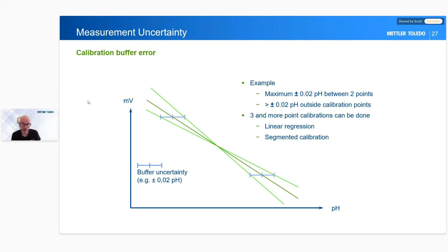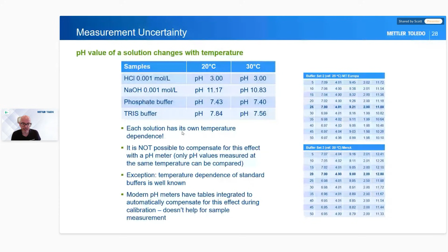The same with temperature. Each sample and solution has its own different temperature. Now for buffers, we know what they are because we've well measured them. And these tables are actually in our Mettler Toledo meters and in other brands of meters as well. These buffer tables are pre-programmed in, so you know what the temperature dependence is. But on samples, for example, hydrochloric acid, or for this one, sodium hydroxide, you've no idea. It really depends on what's happening. So yet again, that's another measurement uncertainty you need to think about when taking measurements as well.